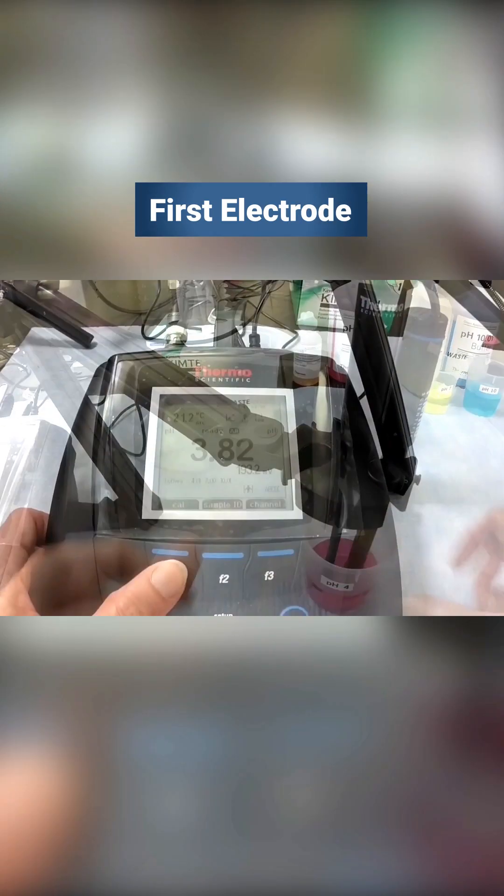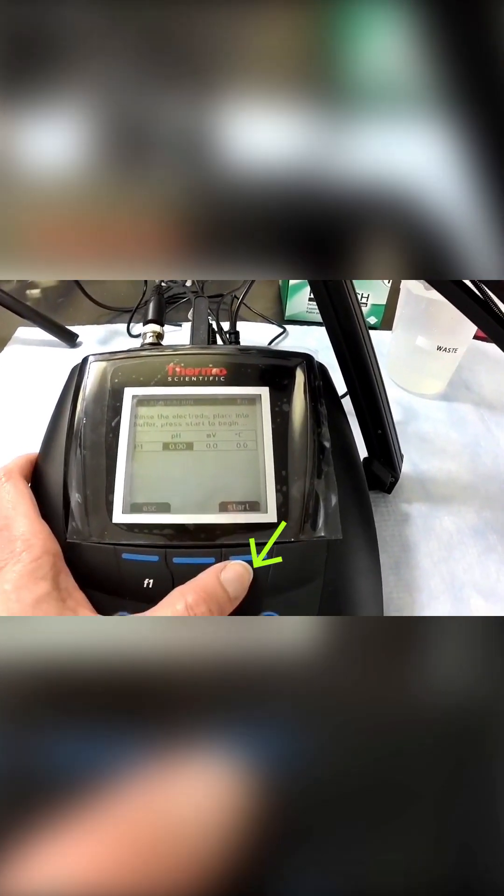Put your electrode into the first buffer. Press the F1 key or the CAL function, then F3 to start the calibration. The pH reading will blink until a stable reading is achieved.